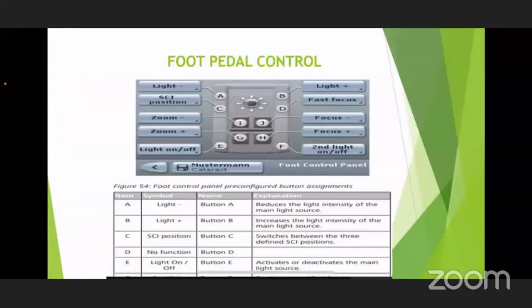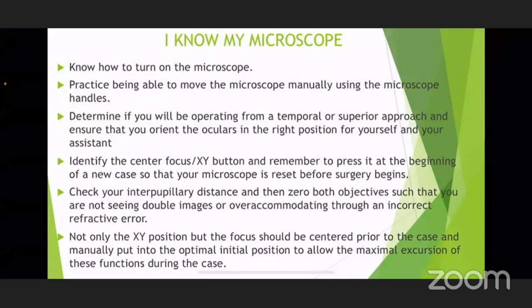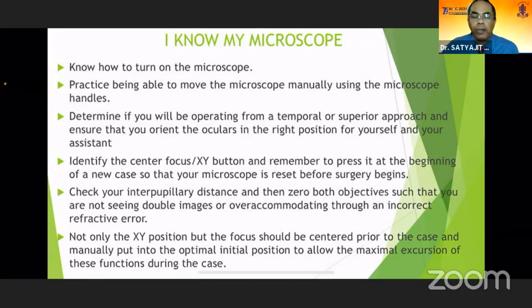It is important that initially the person understands that when starting with the surgery, he should be able to turn on the microscope, manually bring it onto the area of focus, and determine which side to sit — temporal approach or superior approach — depending on the type of surgery. At the beginning of surgery, first center your X-Y joystick control on the microscope body, not through the foot pedal, because the foot pedal is for fine focus and fine changes. Similarly, focus using the par-focality concept at the beginning, so that you do not need to touch the microscope body later. It is all by foot pedal controls. Check your interpupillary distance and zero the objectives so you are not over-accommodating, and dial in your refractive errors. This will allow maximum excursion of these functions during the case. By the end of this training, you should be able to say: I know my microscope.